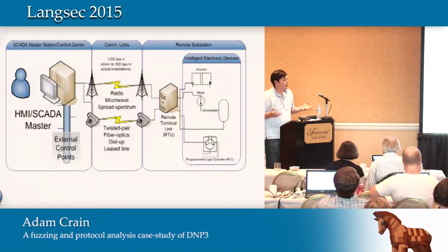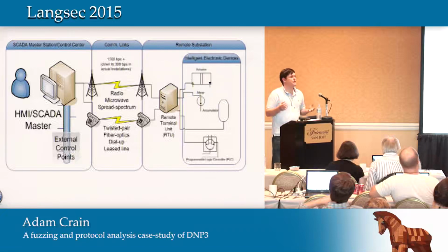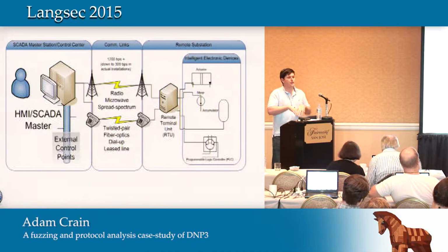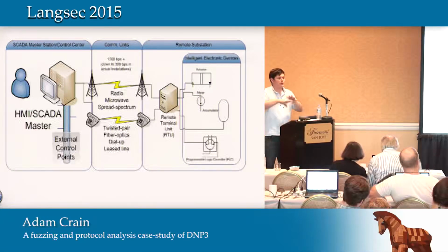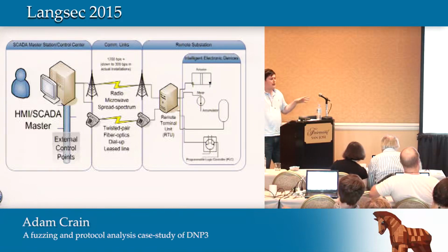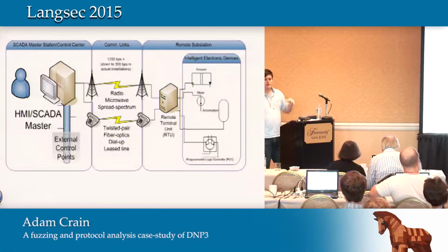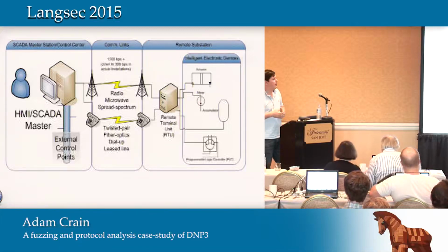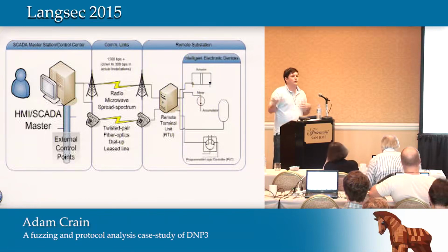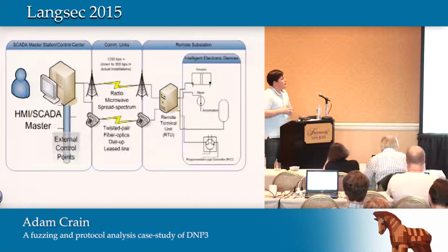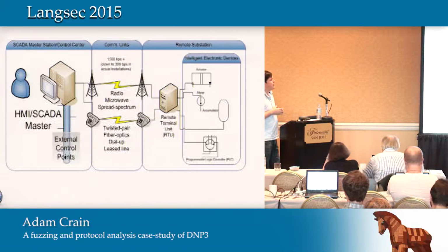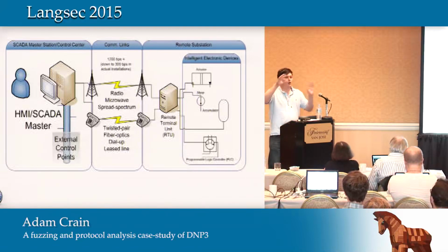SCADA is kind of a subcategory of all industrial control systems, and the characteristics that make it SCADA are generally a couple of things. They're geographically distributed, so you're monitoring some process that is over a large span of areas. You can think about the systems that monitor all the electric substations you have in the field, or maybe you're managing water flows in a water system. And the communications are generally hub and spoke and centralized.